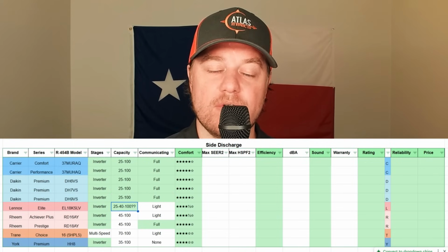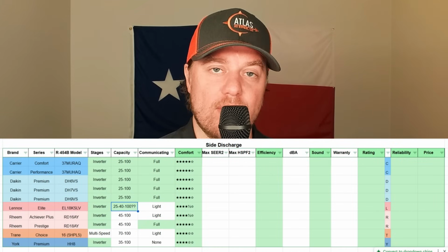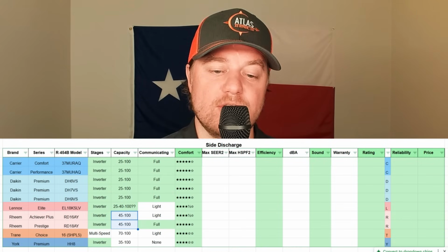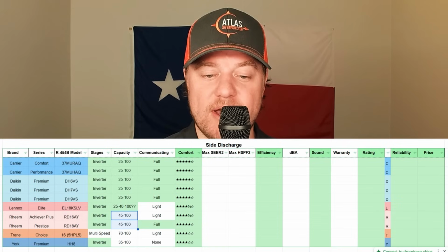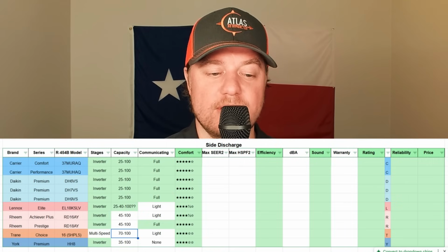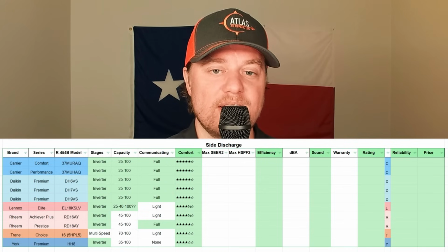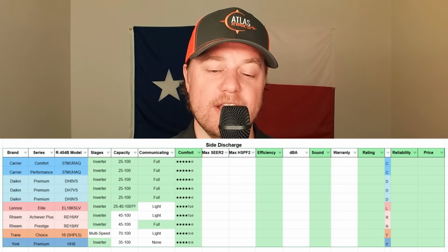The Lennox, however, I'm not completely sure on, and that's because they don't market their operating ranges. However, I do know their operating ranges are going to start anywhere in between 25% up to 40%. And Rheem is going to operate anywhere in between 45% all the way up to 100% working capacity. And Trane is going to perform anywhere in between 70 to 100% working capacity, and York starts at 35% up to 100% working capacity. So the lower the working capacity that these systems can operate at, the better the temperature and humidity control that you can get out of these systems.